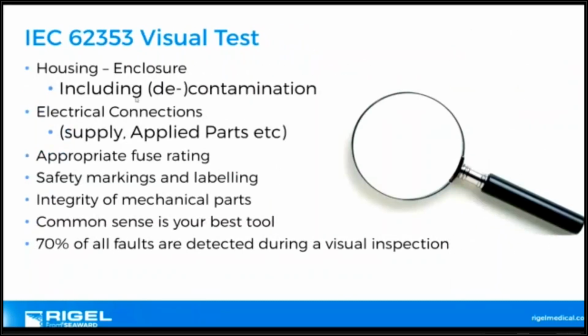The visual check, what are we looking for? We're looking for contamination. We're making sure that all of our plugs, leads, any applied part, anything really that has this isolation barrier, this insulation barrier from a conductive part, is intact, is not damaged. We're looking at appropriate fuse ratings, because if you have a device that states on the back of the device 1 amp, but you've got a 13-amp cable, let's say it doesn't have internal fuses. You've got a different fuse in the device.